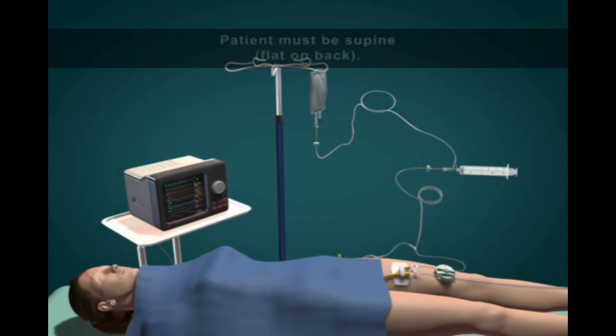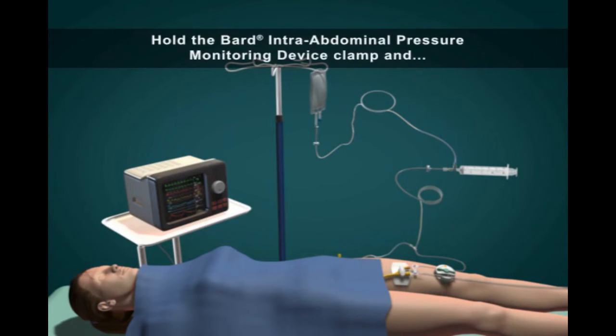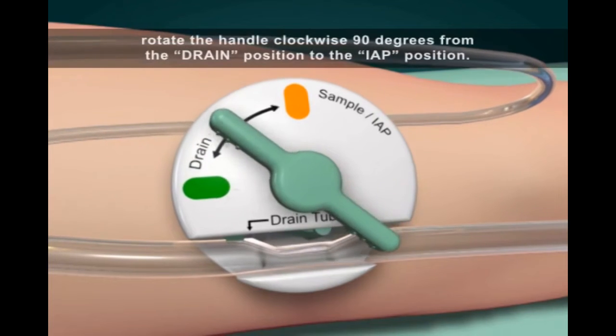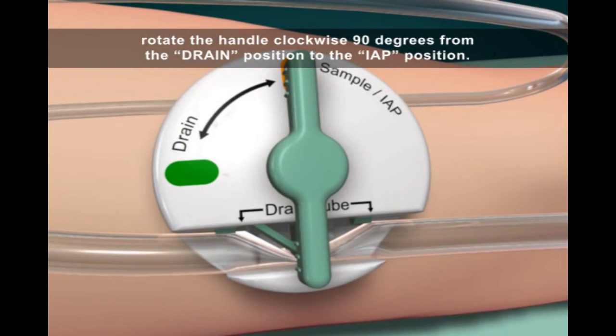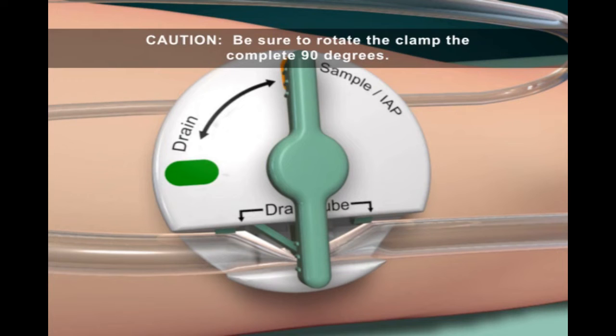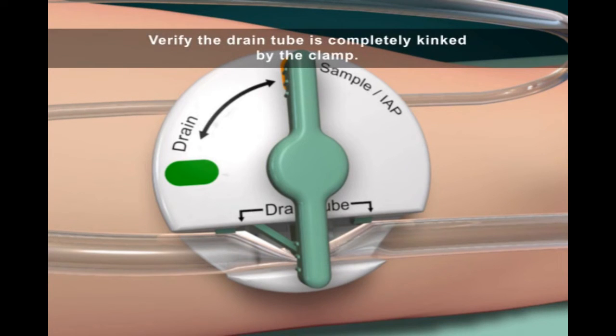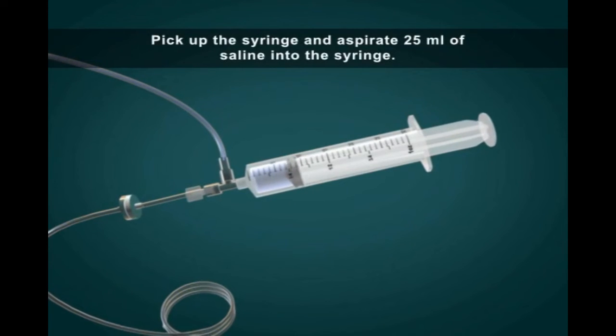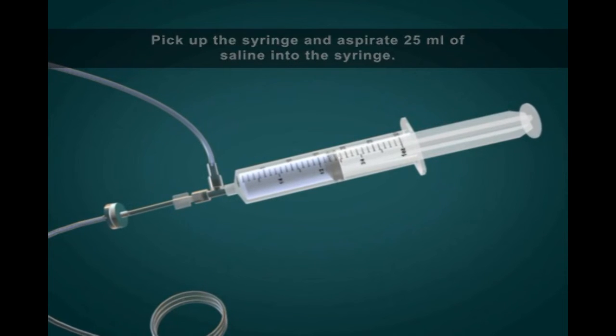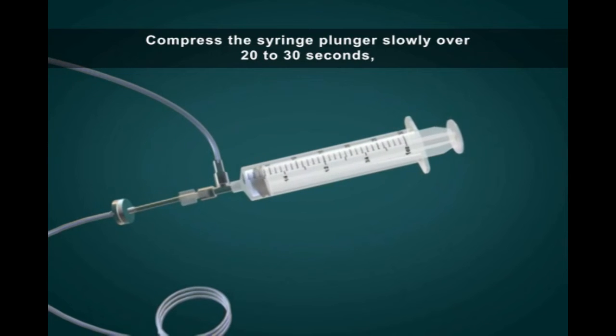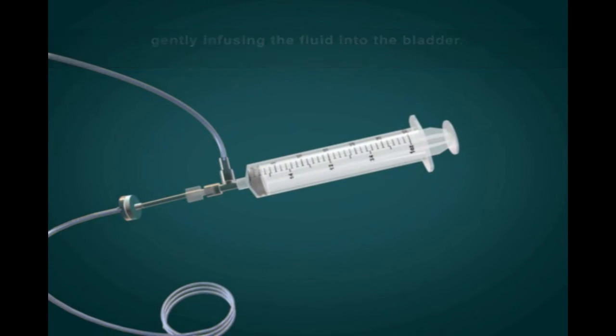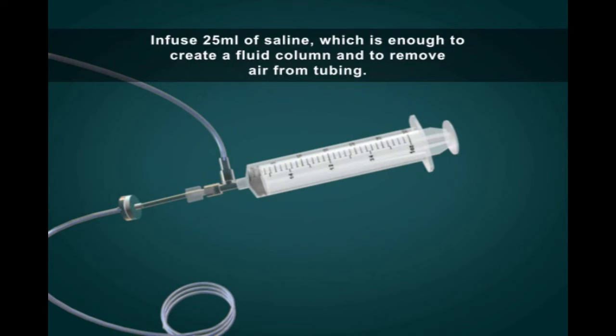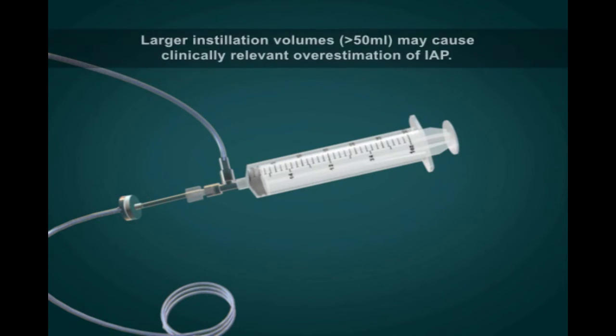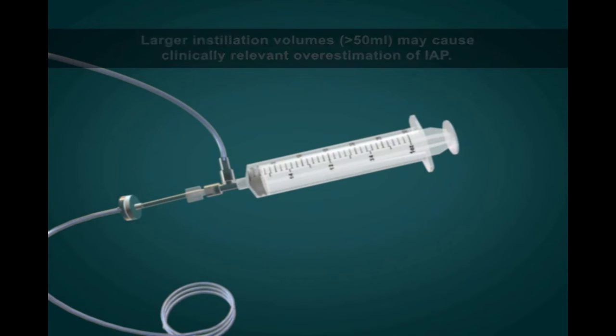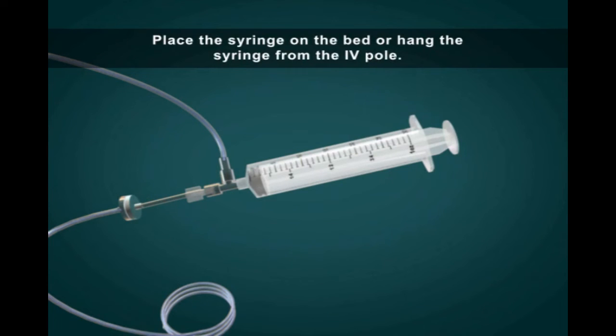Obtaining an IAP reading. The patient must be supine. Hold the device clamp and rotate the handle clockwise 90 degrees from the drain position to the IAP position. Caution: be sure to rotate the clamp the complete 90 degrees. Verify the drain tube is completely kinked by the clamp. Pick up the syringe and aspirate 25 milliliters of saline into the syringe. Compress the syringe plunger slowly over 20 to 30 seconds, gently infusing the fluid into the bladder. Infuse 25 milliliters of saline, which is enough to create a fluid column and to remove air from the tubing. Larger instillation volumes, greater than 50 milliliters, may cause clinically relevant overestimation of IAP. Place the syringe on the bed or hang the syringe from the IV pole.